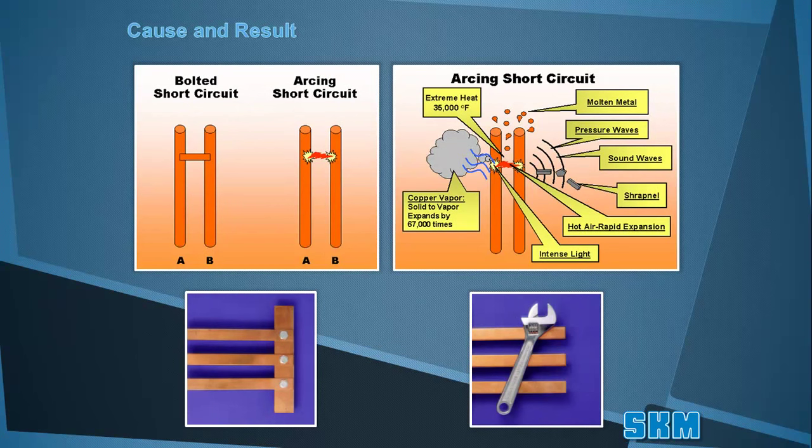Arc flash risk assessment estimates incident energy exposure from potential arc sources. To understand the purpose of an arc flash study, it is important to understand the difference between a traditional fault and an arcing fault. A bolted three-phase, phase-to-phase, or phase-to-ground fault creates high current that flows through the network and the current is contained within the network. Traditional fault studies are used to select equipment that can withstand and interrupt these short circuit currents.